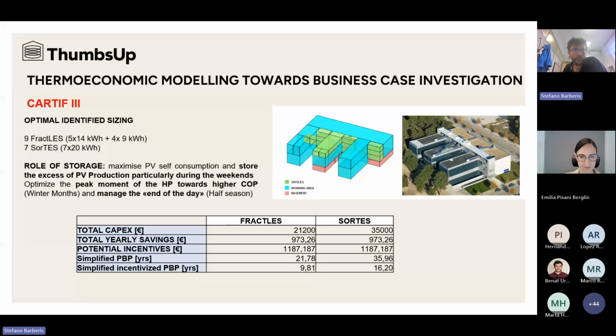For example, in the case of CARTIF, the role of storage was mostly to maximize PV self-consumption and store the excess PV production, particularly during weekends. Another role was to optimize the heat pump operation during peak demand moments towards a higher COP, moving closer to the nominal COP. Since the building is not in use on weekends, the idea was to maximize operation during the weekend, exploiting PV production that would otherwise be wasted, as well as optimizing energy efficiency.